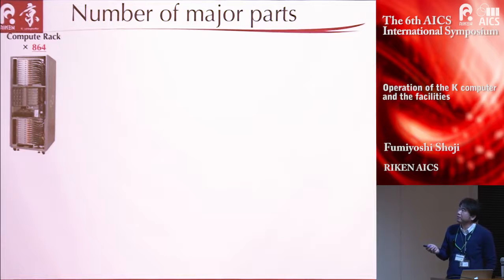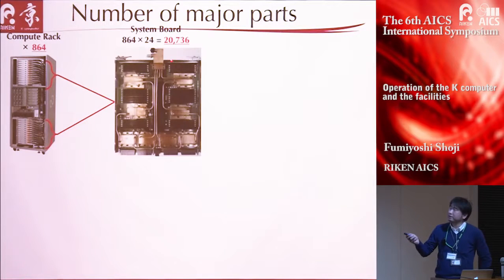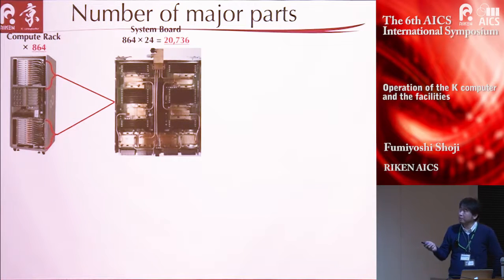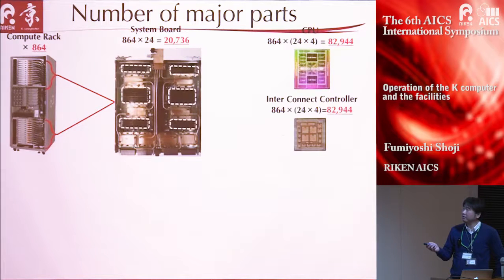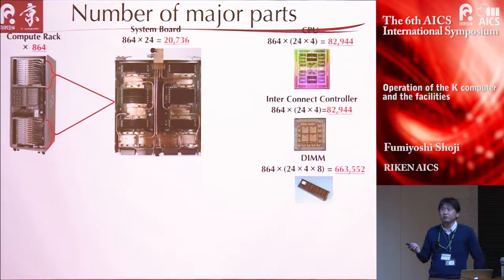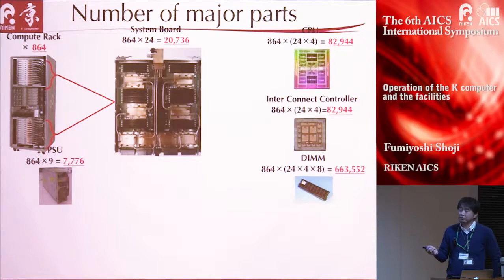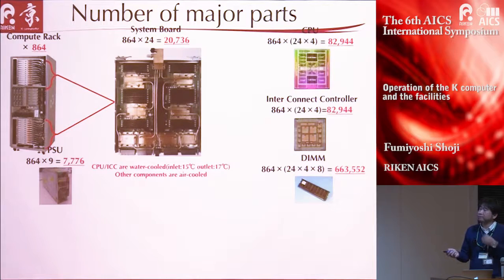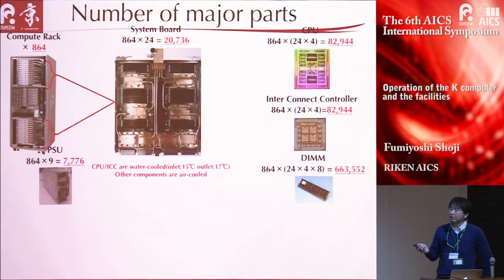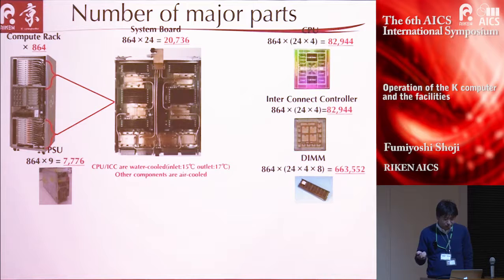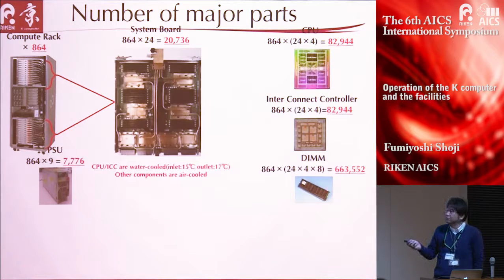The K-computer consists of 864 computer racks. Each rack has 24 system boards, so the total number of system boards is large. Each board has four CPUs, four ICCs, and 32 two-gigabyte DIMM modules. Each rack also has power supply units. CPUs and ICCs are water-cooled, with inlet water temperature of 15 degrees Celsius and outlet about 17 degrees. Other parts, including DIMMs, are air-cooled.